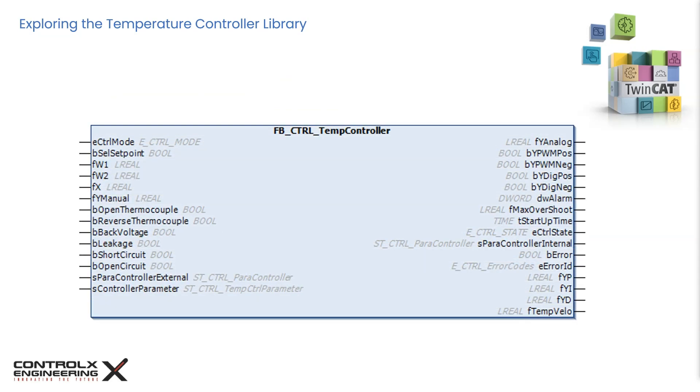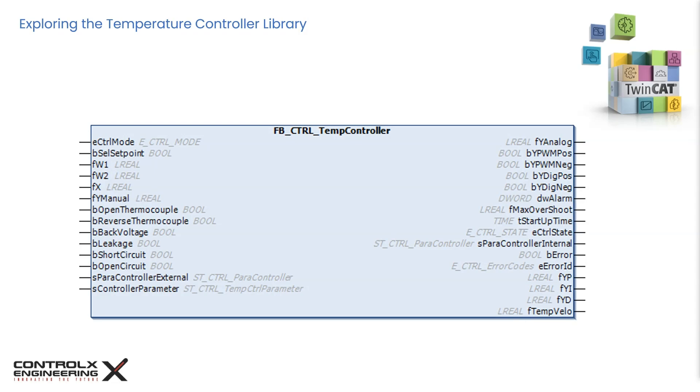It is a universally applicable PLC function block for monitoring and controlling a wide variety of temperature dependent processes. The controller can be operated in both automatic or closed loop as well as manual or open loop modes. The control value can be accessed in digital or analog form. The digital form value is a pulse width modulated signal and perfect for firing solid state relays for heaters. A two-point or three-point output is also available. The controller value is limited to the permitted maximum and minimum values as defined using parameters which we will cover shortly.